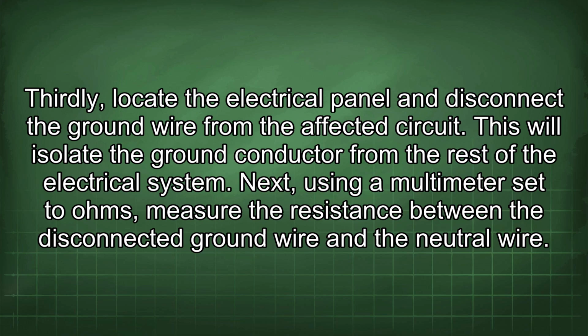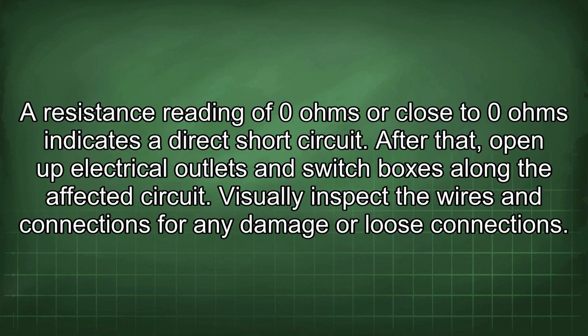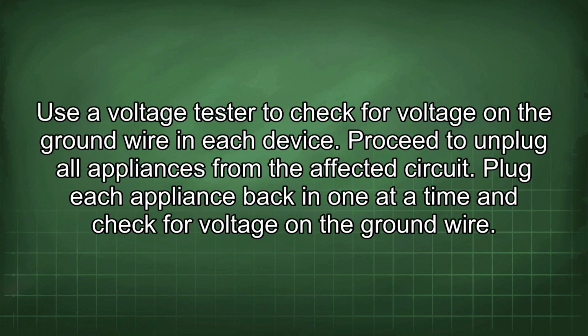Next, using a multimeter set to ohms, measure the resistance between the disconnected ground wire and the neutral wire. A resistance reading of 0 ohms or close to 0 ohms indicates a direct short circuit. After that, open up electrical outlets and switch boxes along the affected circuit. Visually inspect the wires and connections for any damage or loose connections. Use a voltage tester to check for voltage on the ground wire in each device.